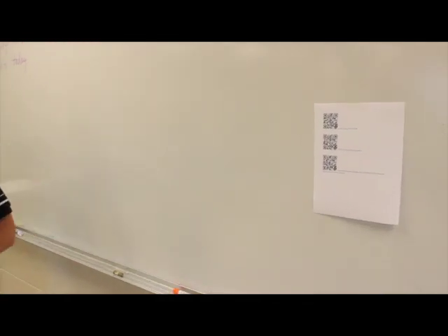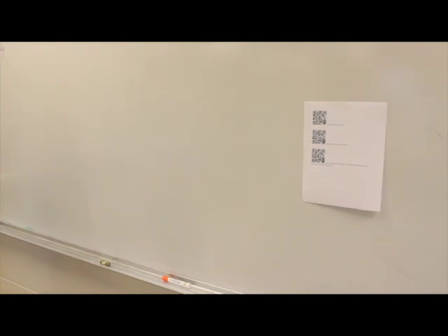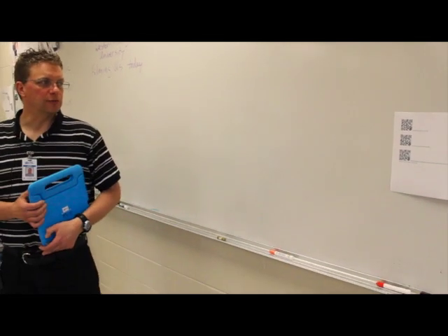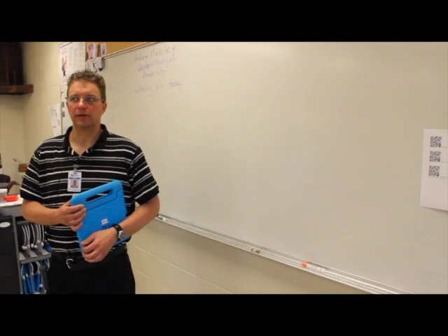The first one on the bottom deals with some motors that we have here in the building, and I'm trying to make it a little bit more realistic, where they're coming into a welding shop or maybe a maintenance facility, or in our case the boiler room here in the building. They're going to have to look at the nameplate of the motor and at the different voltages the motor's powered at. Then, using the lessons that we've been doing this week, after watching the video, they're going to answer the questions that I prepared, and they'll actually figure out the correct fuse or the correct circuit breaker, and then also determine the overload protection that they might need as well.